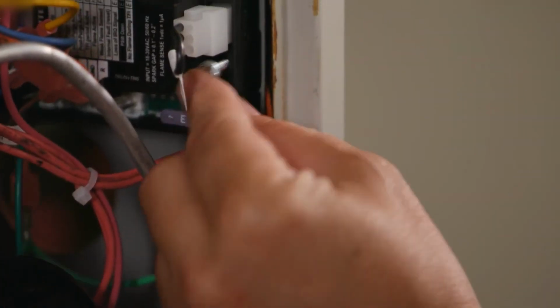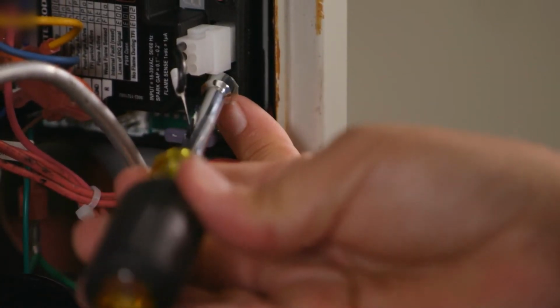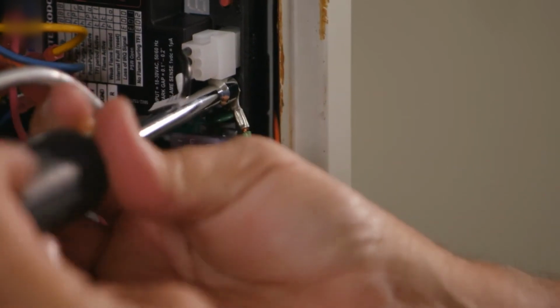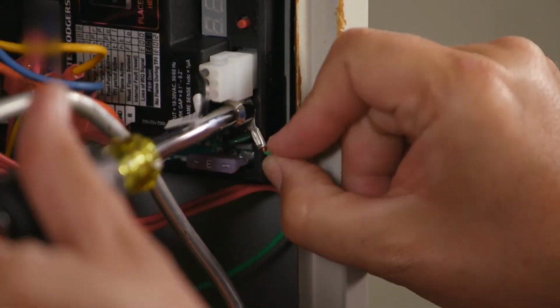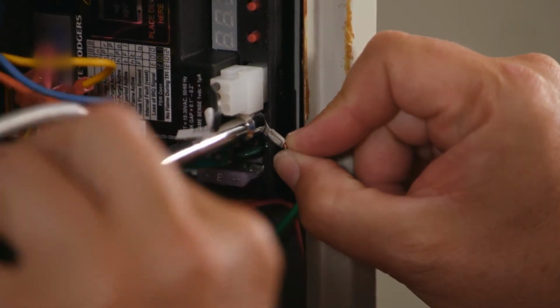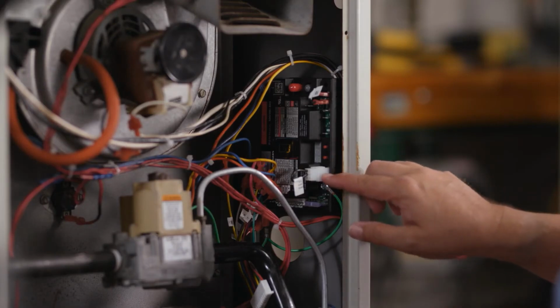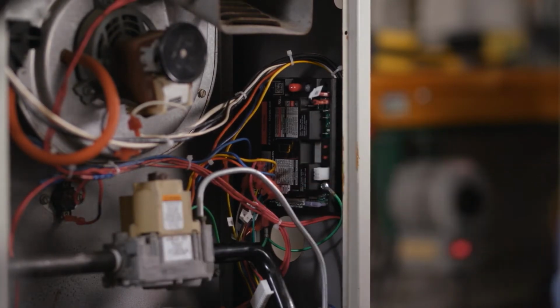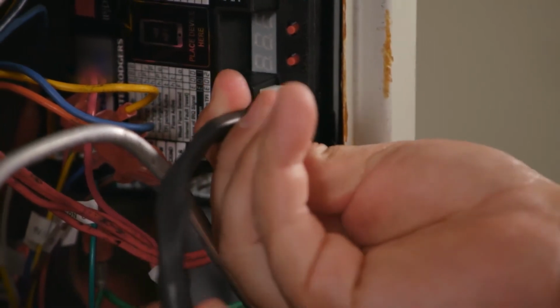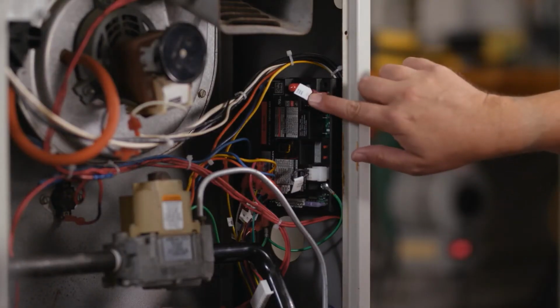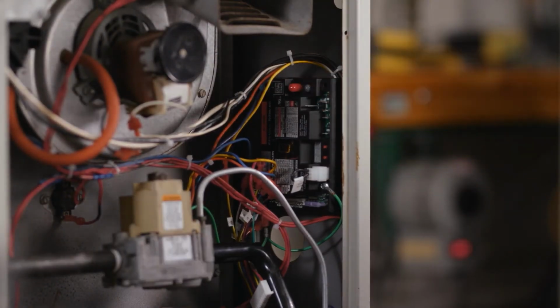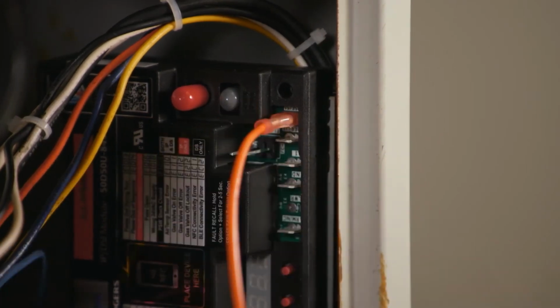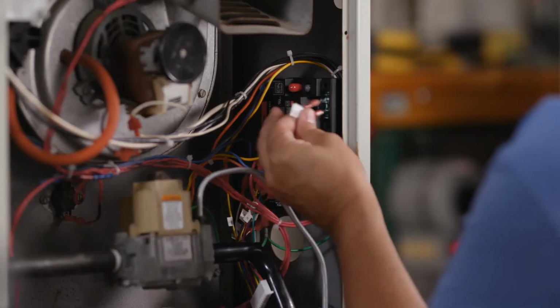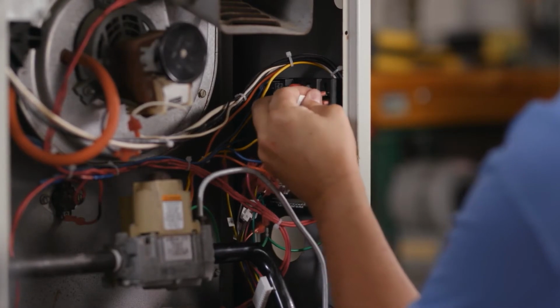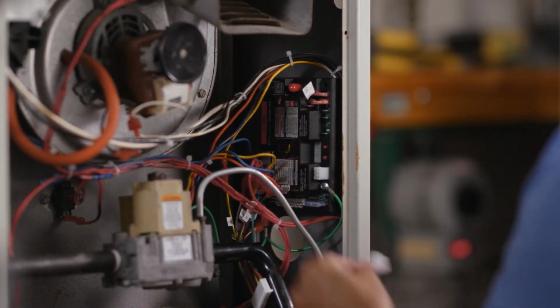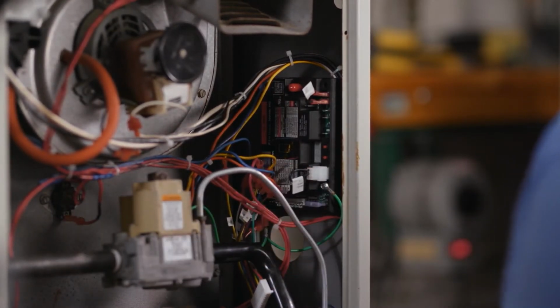For this application, there is a ground wire that needs to be installed. Be sure not to damage any components such as transformers, wire harnesses, or blower wheels when drilling or installing screws. For applications using a vent damper, remove the vent damper jumper plug and install the unit connector. In applications using a remote flame sensor, remove the flame sense jumper and plug the flame sense wire into the sense terminal. For this application, no damper or remote flame sense is used. The vent damper jumper plug and local flame sense jumper wire can be left on the control.